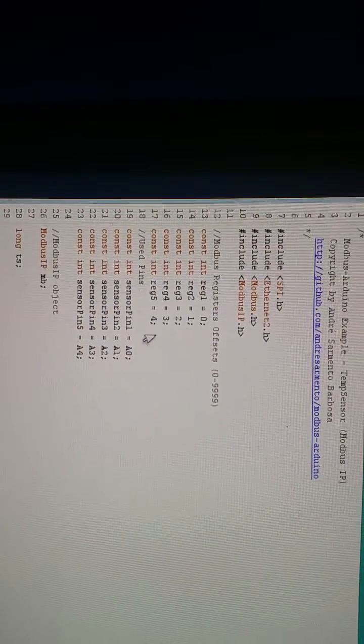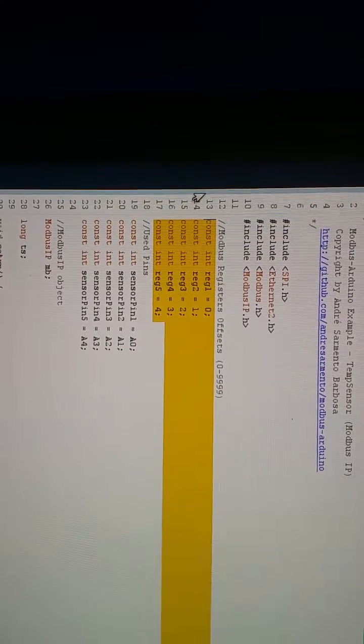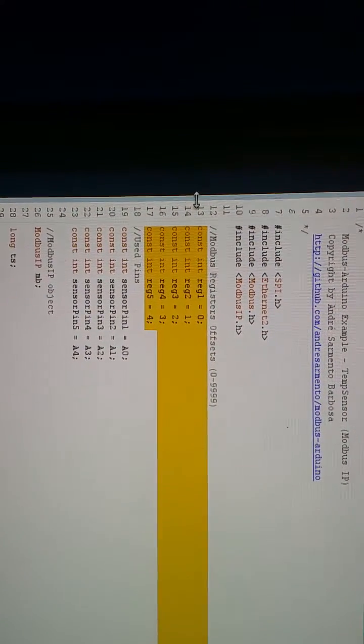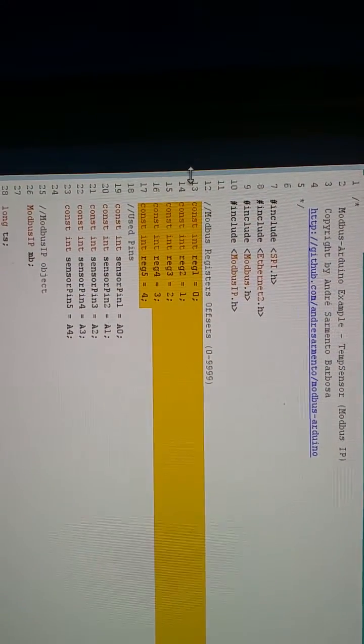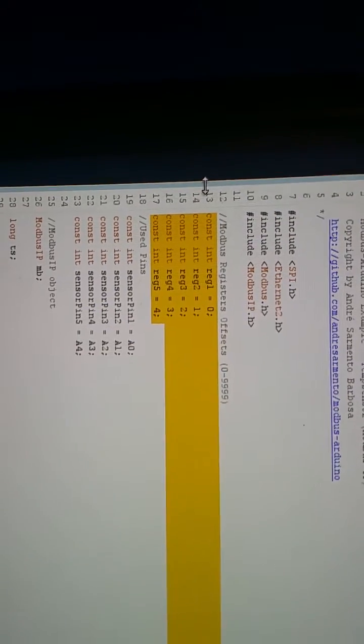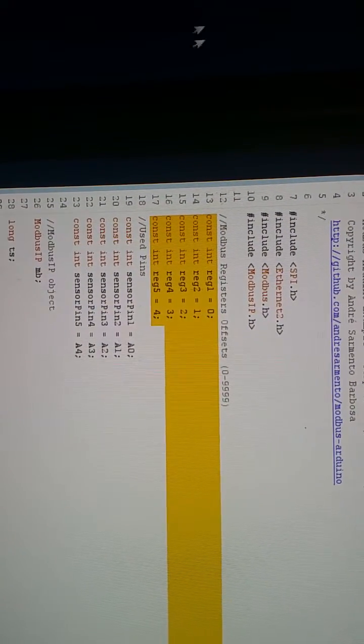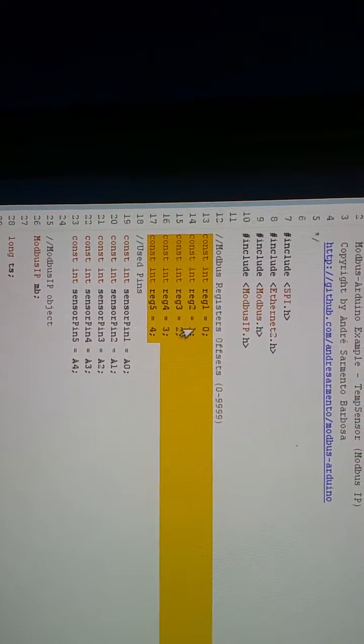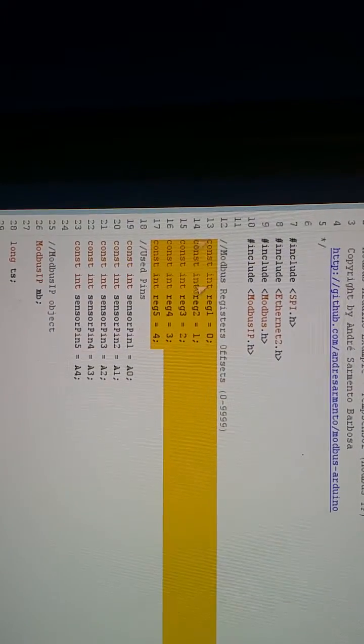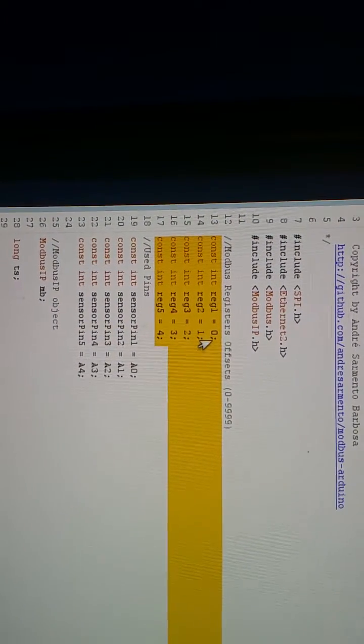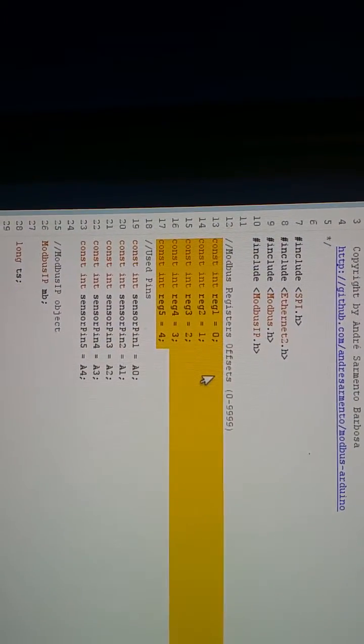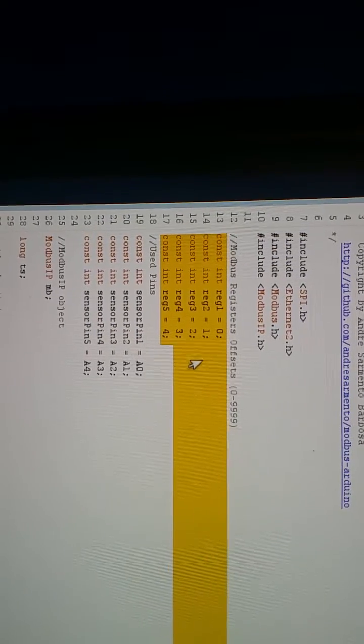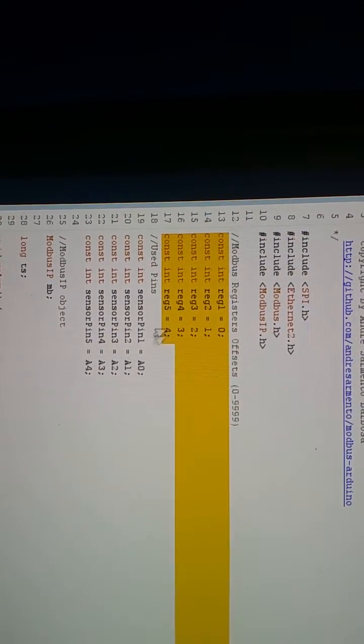Really what I did is I added four registers. These are holding registers. And when you set these up, you only set up the number, the final number of the register and it's base zero. So zero really becomes 40,001, 40,002, 40,003, et cetera.